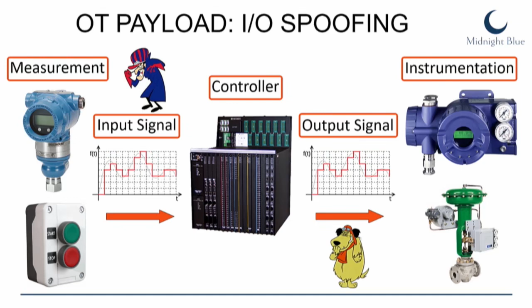Now, internally, this looks like this on these devices: you have the physical I/O, you have the logic, and there's an intermediary variable table that manages this. On the Triconex, this is handled by an I/O processor with a shared memory connection to the main microcontroller, where it places this variable table. We didn't have a Triconex controller, but we did have a Wago PLC, and it basically comes down to the same thing.